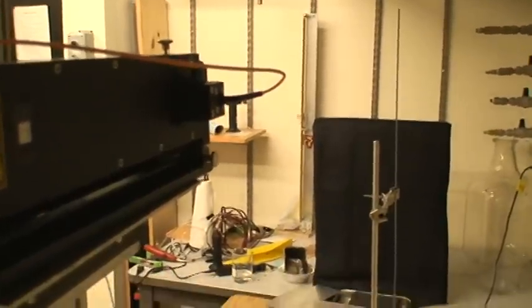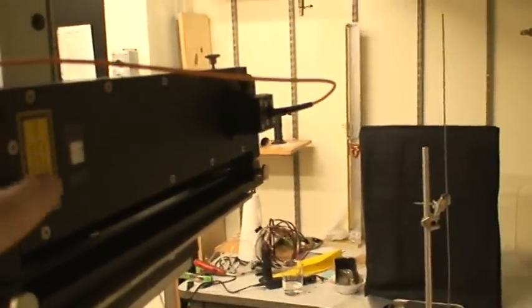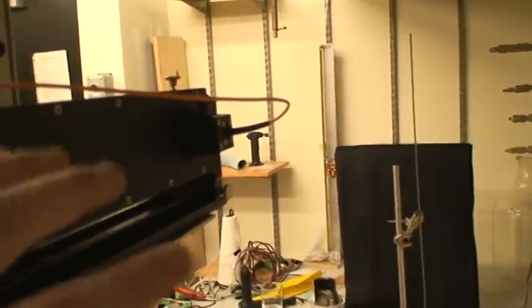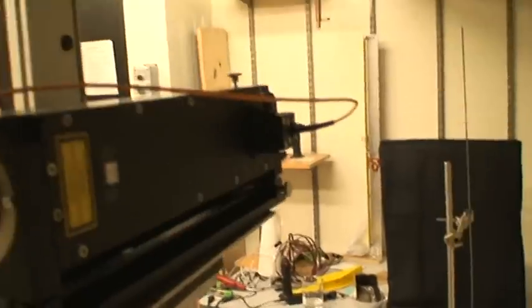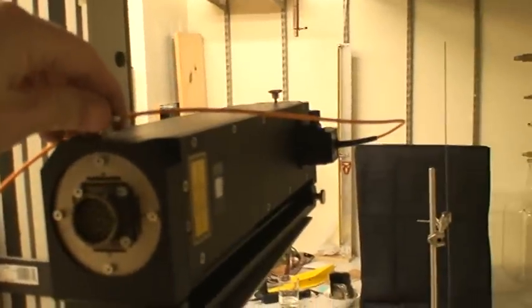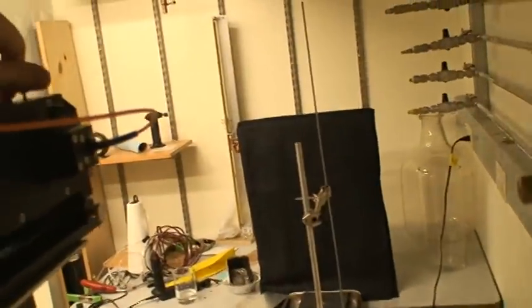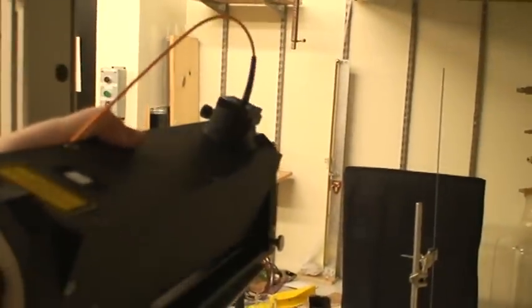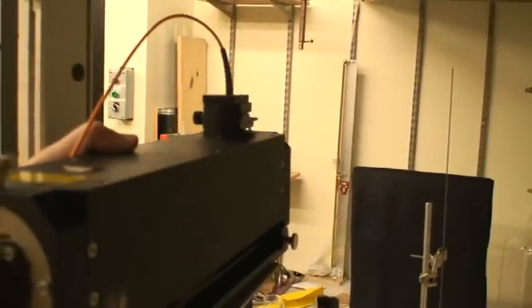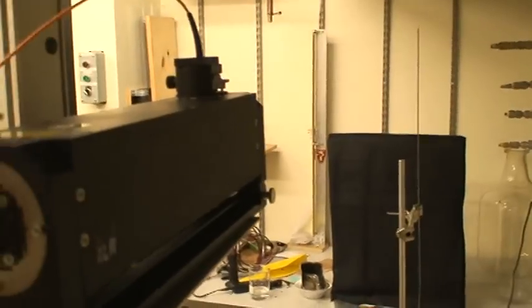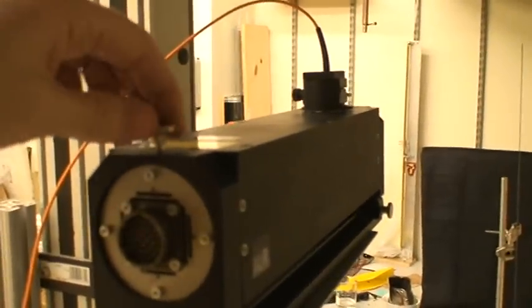If you want to change this axis or the measurement axis, you can loosen these bolts on top. There's two of them, and rotate the whole laser assembly around, so you can move it. That can control either way.